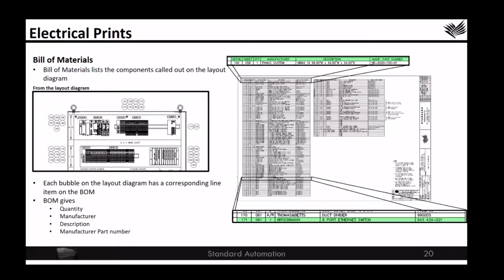Now, we looked back at the layout diagram and we saw, for example, that we have this Ethernet switch located on the right, and it's labeled with a bubble 171. Now, if we go to the BOM, we can see that under detail 171, which is what this indicates on the layout diagram, there's only one quantity of them. The manufacturer is Hirschmann, and its description is an 8-port Ethernet switch, which is exactly what we see located on the layout diagram. Each bubble on the layout diagram has a corresponding line item in the BOM. The BOM gives the quantity, the manufacturer, the description, and even the manufacturer part number so that the item can be readily reordered if in fact it fails.